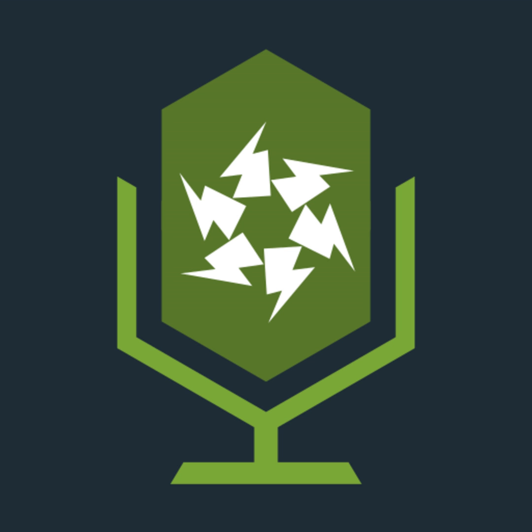So, a lot of people go, oh, bonding's 10, bonding's 10, bonding's 10. It depends on the earthing system. You can't just say, oh, that earth needs to be 10 mil if it's 6 mil. If it's a TN-S or a TT, it's fine.